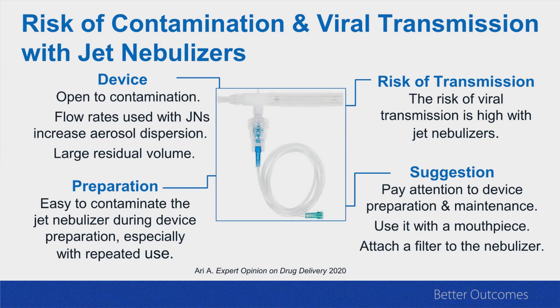The other problem with this nebulizer is the large residual volume. When I say residual volume, I'm talking about the amount of drug that stays in the nebulizer reservoir after the treatment. It is called that because it never goes to the patient. It never aerosolizes after the treatment. So if your job as a clinician is to clean the nebulizer after each treatment, but if you forget to do that, residual volume will stay there and may create a hospitable environment for pathogens.